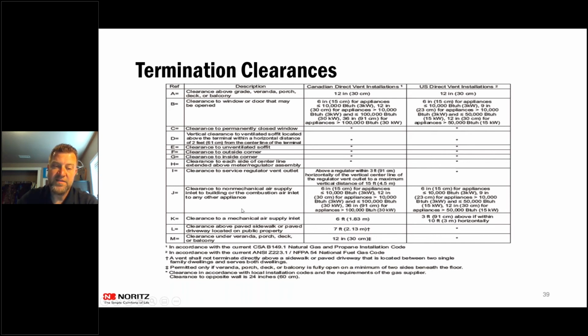So a lot of inspectors have gone and looked at the K and said, look, you need to be 3 feet above or 10 feet to the side, when that's not the case when they're bringing their own combustion air into the house directly through the pipe system into the unit. So that's one thing I want to clear up with everybody. That right there is the two differences. J is if it's an appliance that's bringing combustion air through its own pipe into the house. K is if it's a great big louver that's bringing combustion air for multiple appliances inside the house.